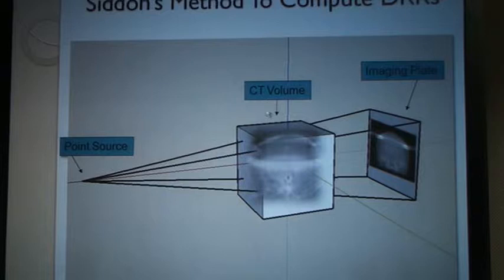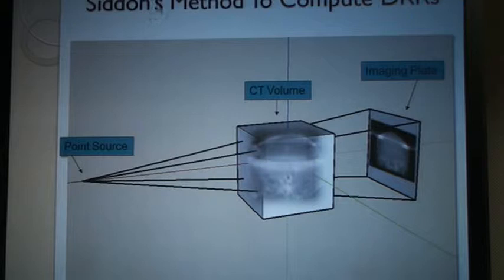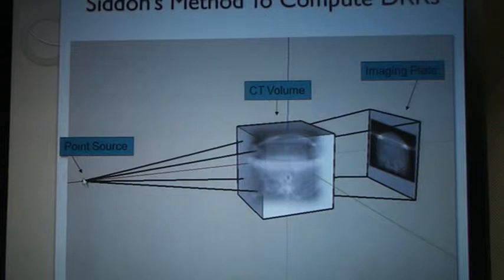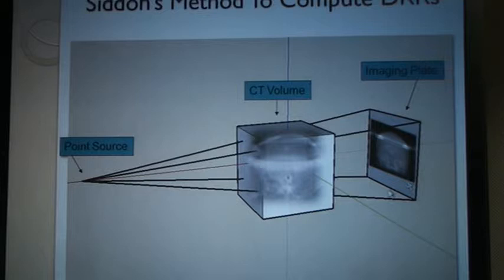Normal ray tracing would be way too slow — it would take hours to compute a DRR that way. The Siddon's Method uses the same concept of ray tracing, but instead of starting at the point source, you work backwards. In reality, photons start at the source, pass through the patient, and land on an imaging plate. You could simulate this with Monte Carlo, but it would take hours and hours to compute just one image.